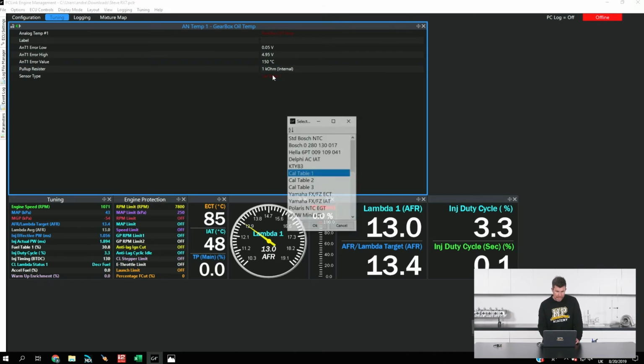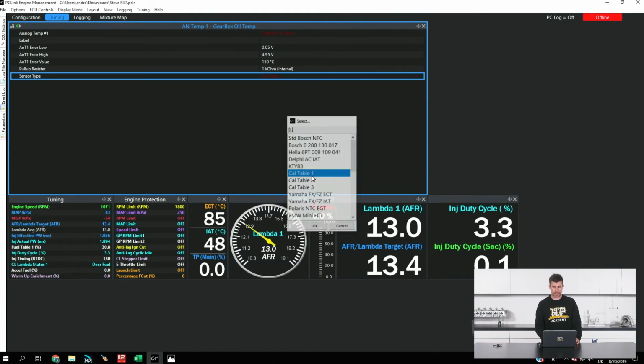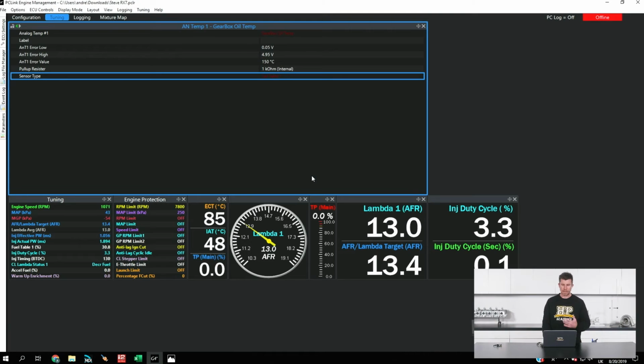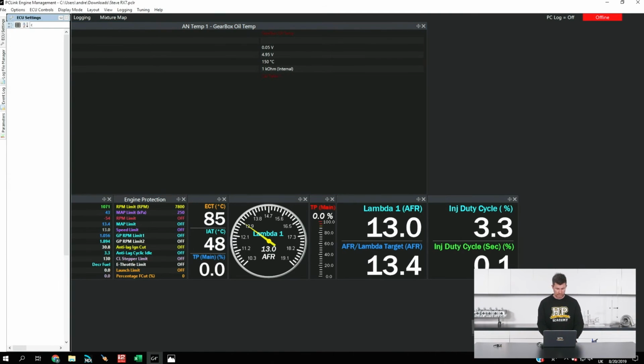We can then go to our sensor type. For the majority of common sensors, there will already be a predefined sensor available. However, we're going to have a look here at using a user-defined sensor. This is where we'd have a data sheet, like the one we just looked at, and set this up ourselves using a cal table. Once we've done that, we need to input some data into the cal table, so let's have a quick look at that.